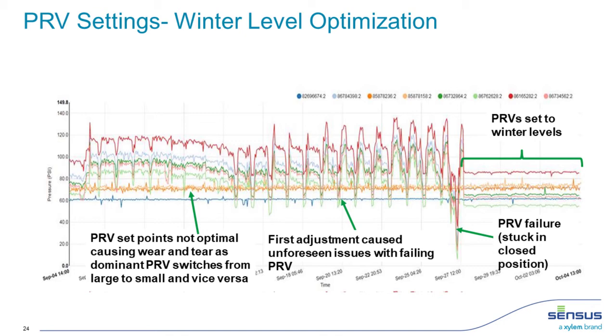What we're looking at is the PRV set points, where a couple of PRVs were fighting each other, the larger and smaller PRVs, resulting in large pressure swings and a kind of slamming when the changes happened. This causes a lot of wear and tear on our assets, and an eventual failure of a PRV in the closed position is likely from that wear and tear.